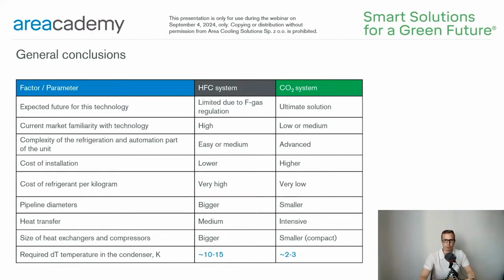Now, when we know more about CO2, let's discuss the main differences between HFC and CO2 systems. We already know that CO2 technology is an ultimate solution, while the expected future for HFC technology is limited due to F-gas regulation. The transition challenge is due to the fact that the current market familiarity with HFC technology is still much higher compared to CO2, for which it is low or medium. CO2 installations are generally more advanced in terms of complexity and automation than HFC systems. Additional security features are required, like safety walls, additional sensors, and so on.